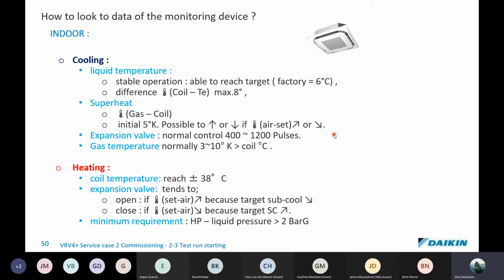Cooling, again, we come back to looking at our liquid temperature, and here we're looking for a stable operation to reach a target or factory set amount of 6 degrees, and a difference in temperature between the coil and the target evaporating maximum 8 degrees. So this is on the indoor. Here, superheat is the gas minus the coil, an initial 5K. It's possible to go up or down depending on the air minus the set point value, and we just discussed that. The expansion valve control in cooling is normally between 400 and 1,200 pulses. It is possible to see it come down if there's less load, and the gas temperature is normally between 3 and 10 K greater than the coil temperature.